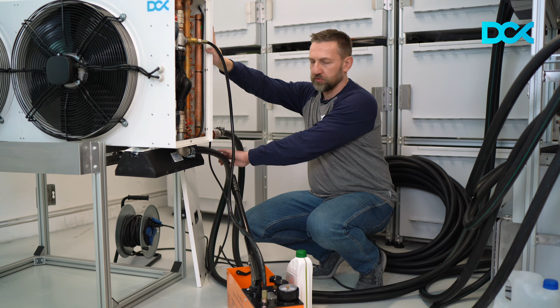We connected that with the one-way valve. We can separately first pressurize and release the air from the dry cooler, and then we can open the bottom valve and release the air from the tubing and from the brazed plate heat exchanger. But for now, let's open the valves here. Yep. And let's pressurize the system. You will use a few containers of treated water or demineralized water. Put it inside, flushing that inside of the manual pump.